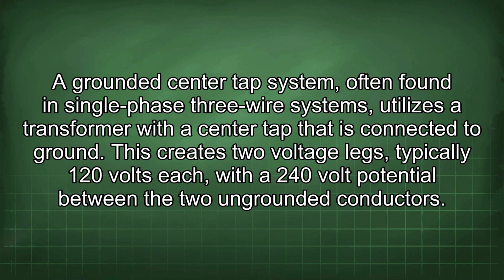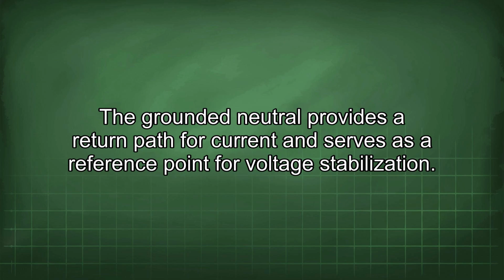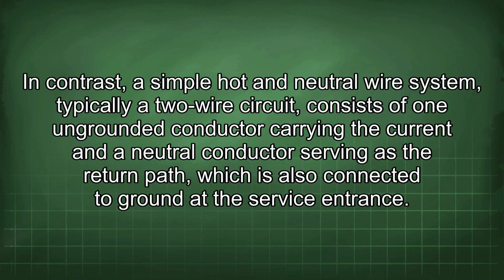connected to ground. This creates two voltage legs, typically 120 volts each, with a 240 volt potential between the two ungrounded conductors. The grounded neutral provides a return path for current and serves as a reference point for voltage stabilization. In contrast, a simple hot and neutral wire system, typically a 2-wire circuit, consists of one ungrounded conductor carrying the current and a neutral conductor serving as the return path, which is also connected to ground at the service entrance.